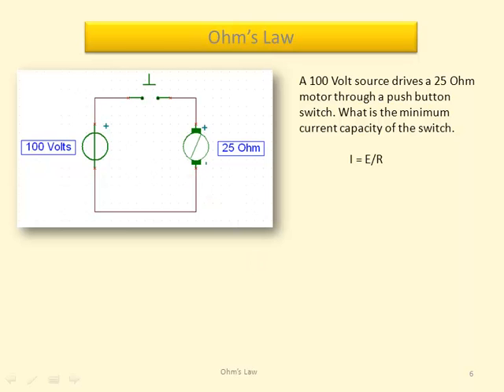Well, we know that current equals voltage divided by resistance. So we take the 100 volts and divide it by 25 ohms, and we get a current of 4 amps. Therefore, the push button must be rated for at least 4 amps.